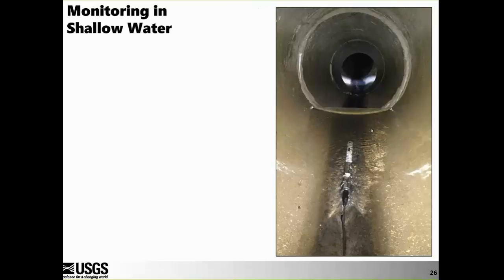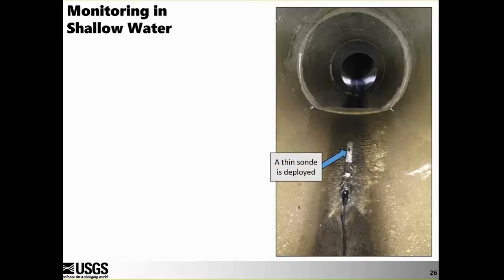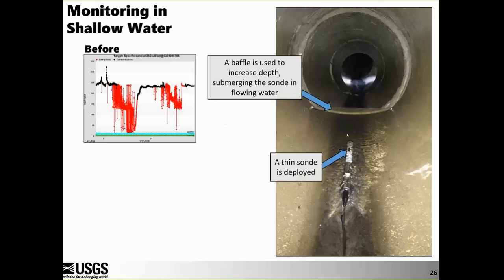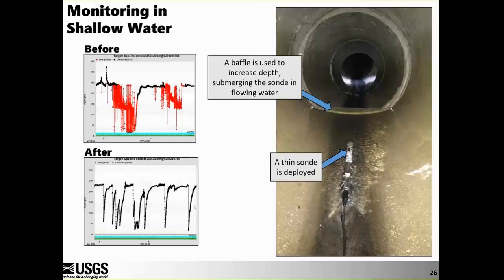One challenge in some environments is monitoring in very shallow water — if probes aren't submerged, you won't collect the data you expect. For a project monitoring stormwater pipes with very little flow at base flow, a thin instrument was chosen, but even that alone didn't produce the quality record expected. The solution was using a baffle upstream of the instrument to increase depth and submerge the sonde more consistently in flowing water, resulting in a much improved record requiring far less oversight.